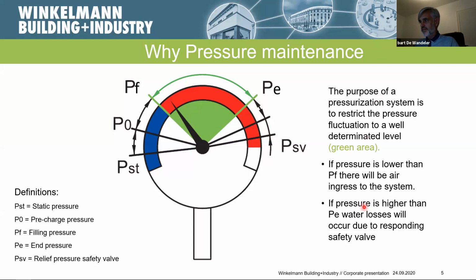I have also made a small text here on the right side, a small presentation of what those pressures are really doing in a system. And you also see that if the pressure here is higher than the P-end, you are going to enter the zone where you can relieve or open your safety valve. But the purpose of a safety valve is, of course, to protect a closed cooling or heating system. This should never go open, never. This is a condition that we have to use to be safe and to be conform in a system. This is also a valve that we cannot see open in a startup or a running phase of a system. Often we do see other things in an installation, but this is related to the whole cycle here being wrongly calculated.